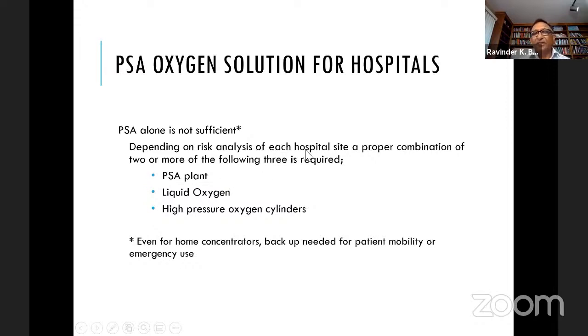So PSA alone is not the solution. What you have to do is a back-of-the-envelope type risk analysis of the hospital site, and then provide backup to that system. The backup could be liquid oxygen or high pressure cylinders, and I'll explain how these are combined and what the limitations are.